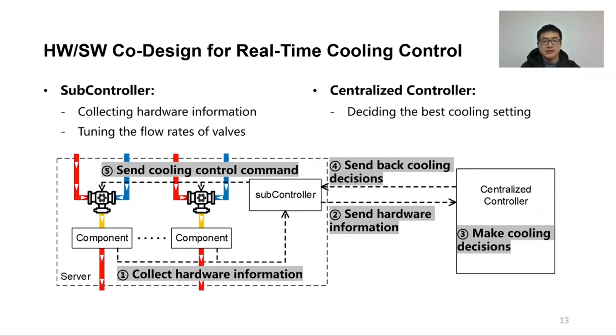The control system is designed for realizing real-time cooling. There are 2 kinds of controllers. The subcontroller first collects all hardware information like power and utilization, and then sends it to the centralized controller. After deciding on the best cooling setting, including the water temperature and flow rate for each hardware component, the centralized controller sends back the cooling decisions. Finally, the subcontroller sends the cooling control command to each valve for tuning its flow rate.